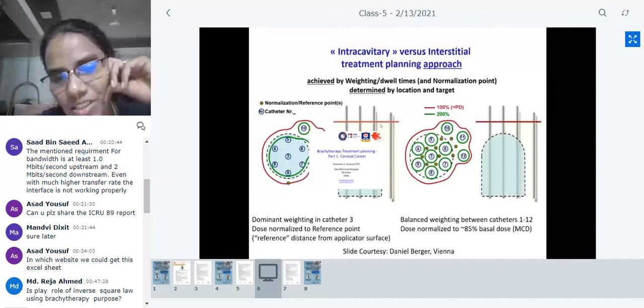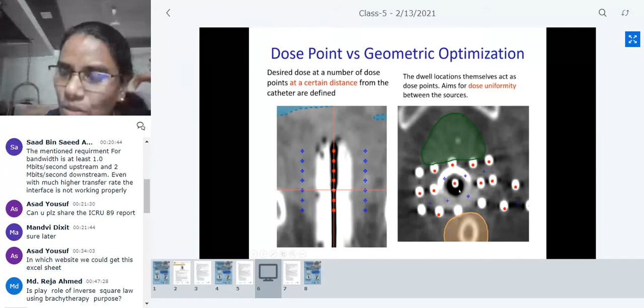Let's say, for example, if you have an applicator here, which is the vaginal cylinder, these are the sources, and this is the vaginal cylinder, and these are the points that you define at a distance from the applicator surface, typically 5 millimeter from the applicator surface. And here, in the case of pure interstitial implants, you are going to have the dose points at the basal points. So these are the basal points based on the Paris system. So these are the points on which you are going to define the dose points. So here in this case, you are going to use the dose point optimization. And here in this case, you will be using the geometric optimization.